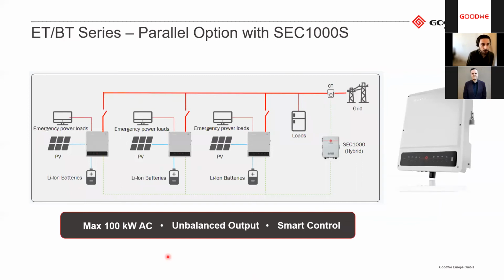Here you see the parallel connection of either the ET or BT series. For this you need the SEC 1000S for hybrid box. You can connect up to 10 inverters to it, for up to 100 kilowatt of AC power. Each inverter then has its own battery, PV, and backup port, so if the grid goes out, each inverter works as an isolated system. When the grid is on, this box coordinates the power production from the PV and battery across the inverters.